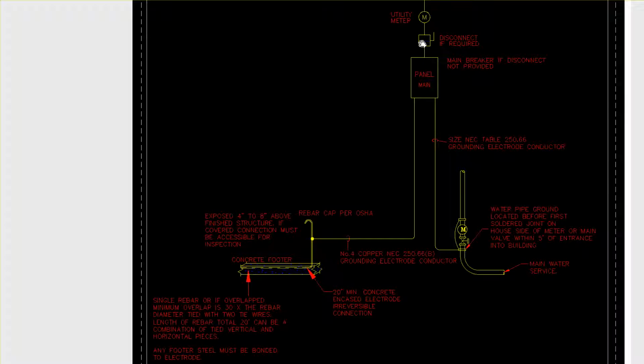If there's not a disconnect, disconnects are required by code on the outside of a building, or really what the code's attempting to do is this piece of conductor that you see here is always got to be protected inside a building or home. That's where there's issue for fire. If this is the meter, and then that meter oftentimes will just set back to back with the main panel and with the main circuit breaker, that gets that accomplished. If that panel is meant to be more interior to the site, then you have the issue of needing to protect that conductor, like I said before. So we would put a main disconnect on the outside, usually with fuses. Those are relatively inexpensive and a good way to get that accomplished.